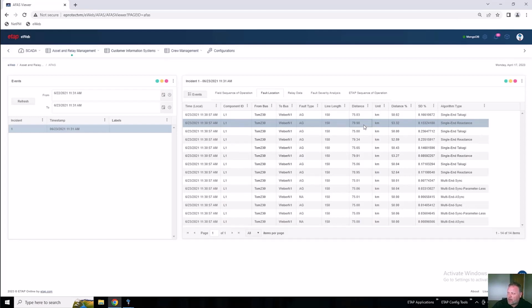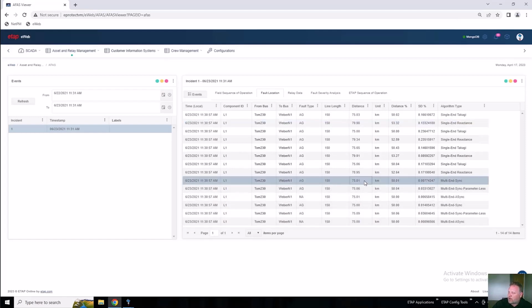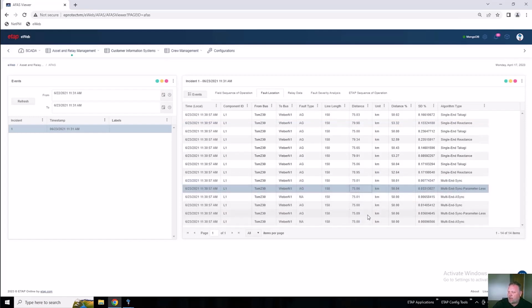The important thing here is that when we're looking at single-ended calculations, these first few are single-ended calculations, they're typically significantly less accurate. That means you only have a relay on one side and you calculate the fault location based on the relay on that one side. Now if I look at my multi-ended calculations, they're all within a very small distance of each other: 75.01, 75.06, 75.09. So these are all very close, indicating the accuracy of the calculations. And this is reflected if you look at the standard deviations. On the single-ended side, the standard deviations are much higher than on the multi-ended side.